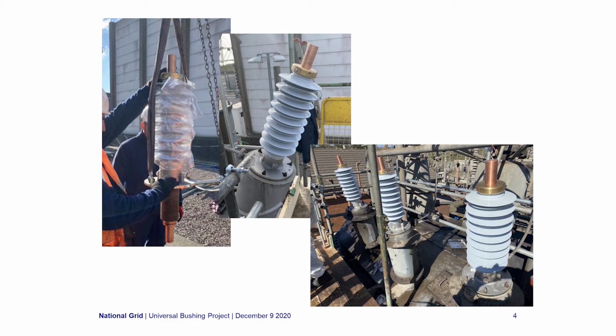Whilst National Grid has already benefited from achieving its goal on this project, we fully expect that the interchangeable bushings that we have developed would work on other transformers with 33 kV connections. In our case, 33 kV is on the LV side, but we anticipate that these could be used on the HV side of other network transformers, of which there must be many in the UK.